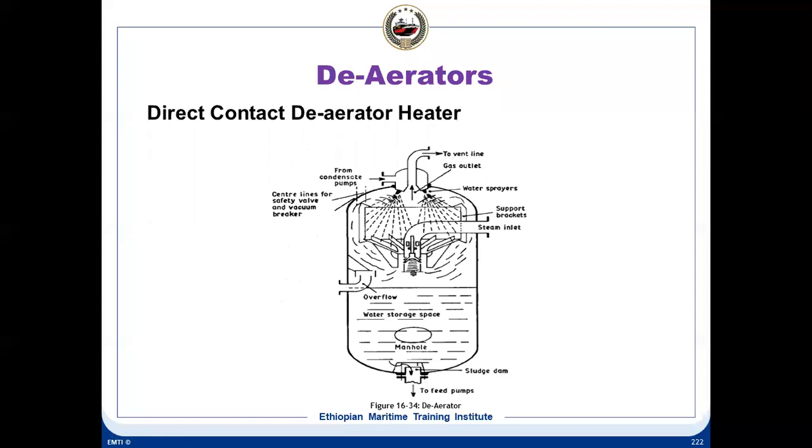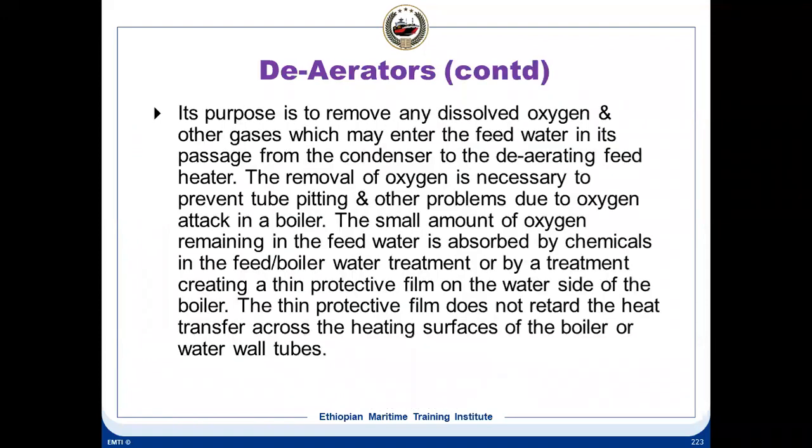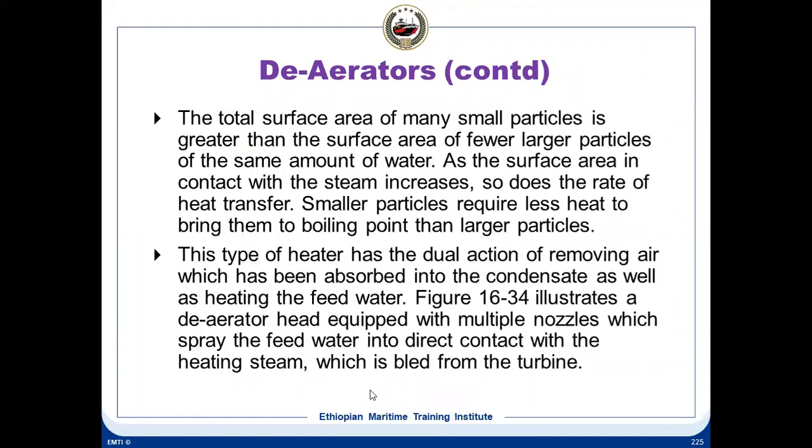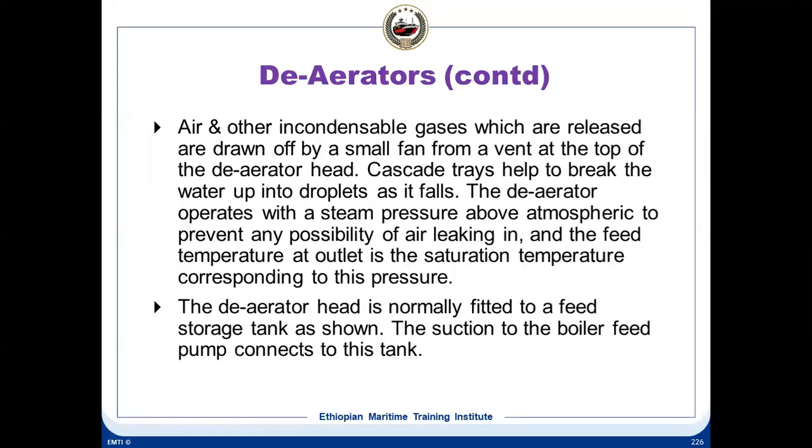I don't think the idea of draining this to the feed water tank is advisable, because in the feed water tank, again, the water is just stored. The temperature will drop and the air can again dissolve back in, recontaminating this condensate. So it should be going back to the hot well. And the heating steam is bled from the turbine. There's small piping, and that steam is the one that comes and heats up the condensate.